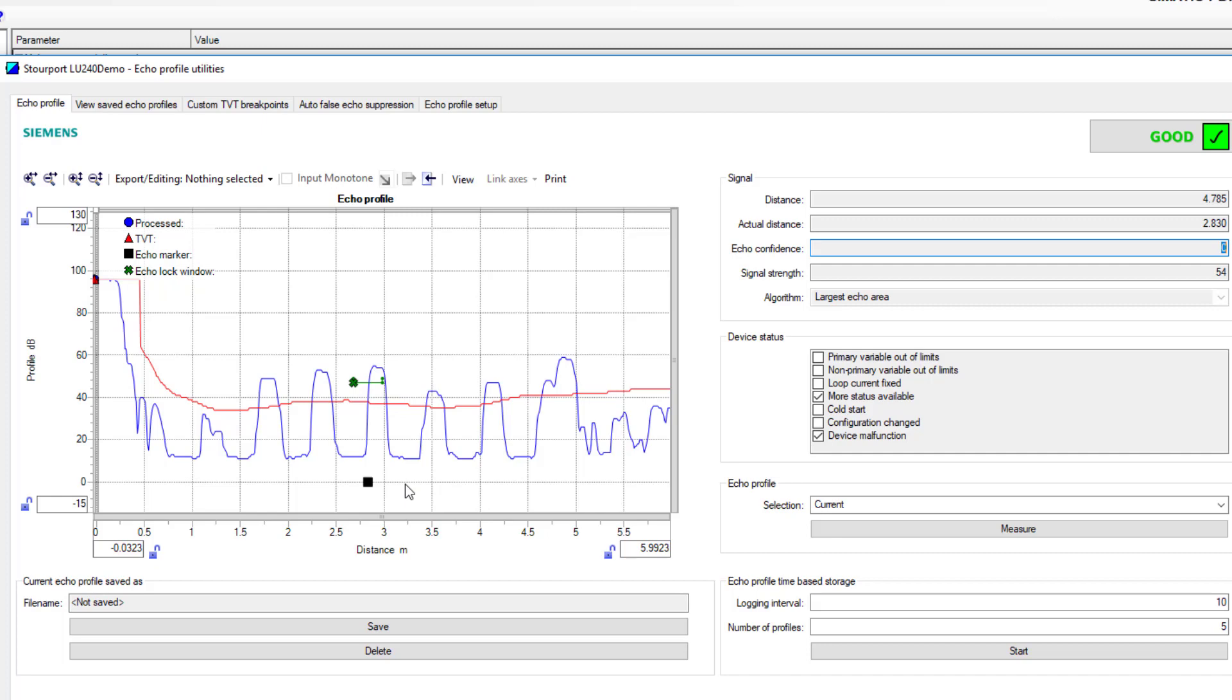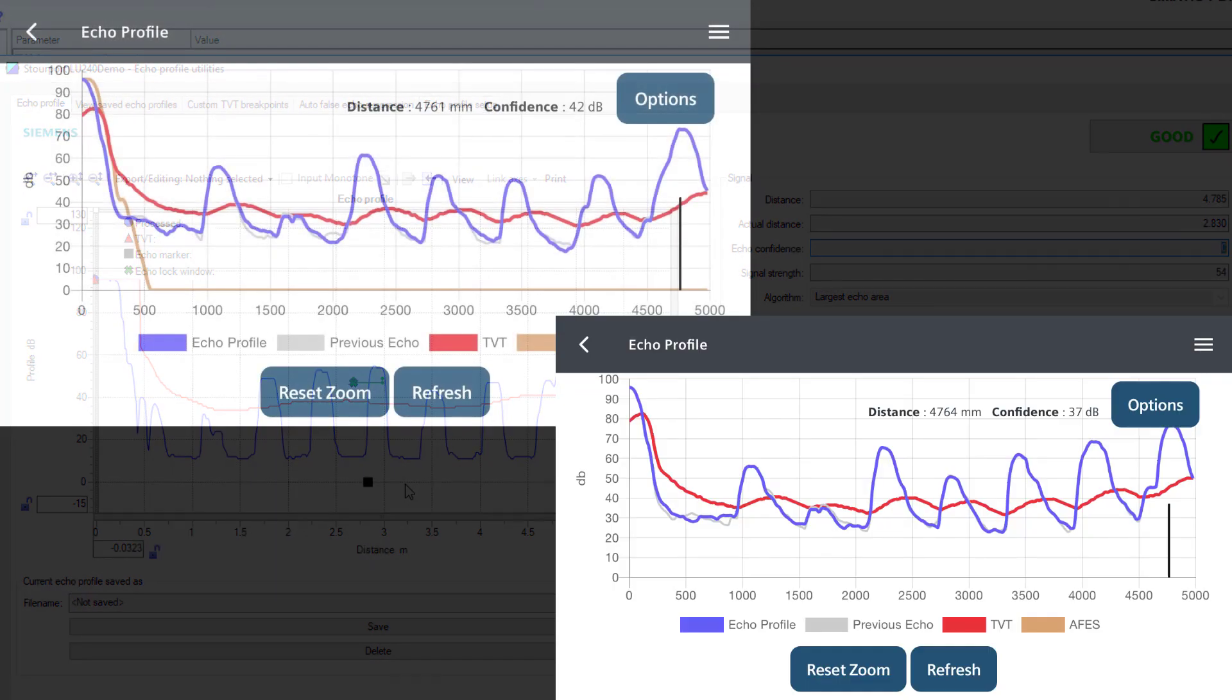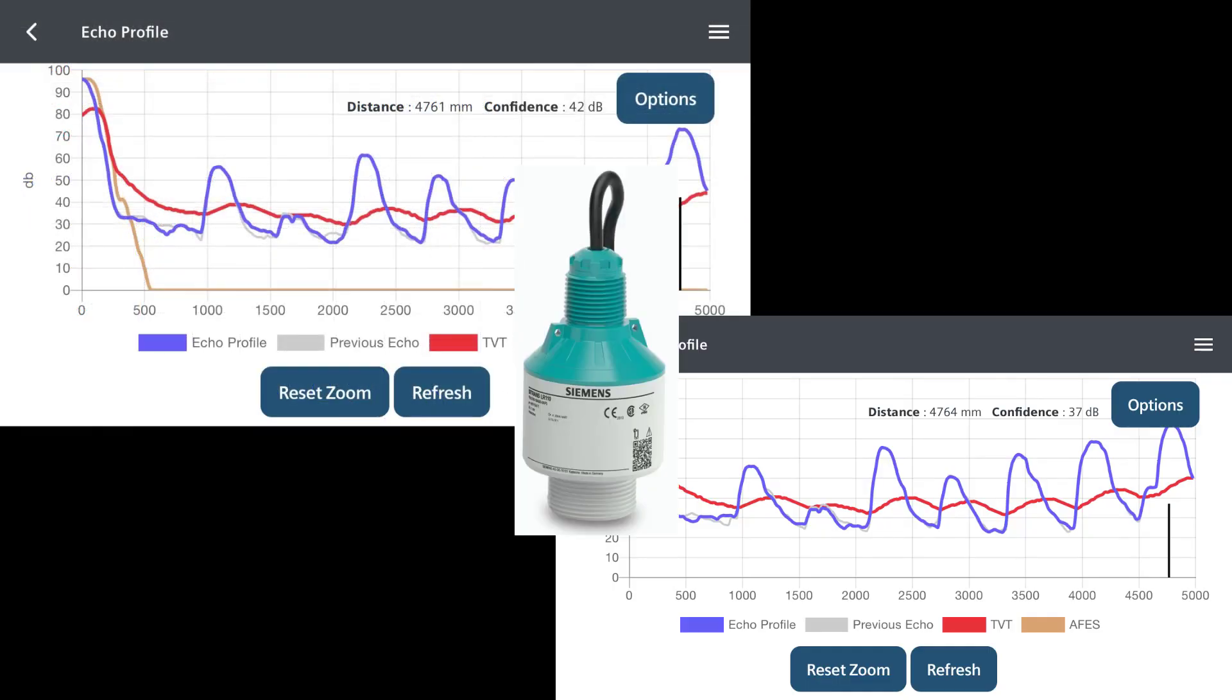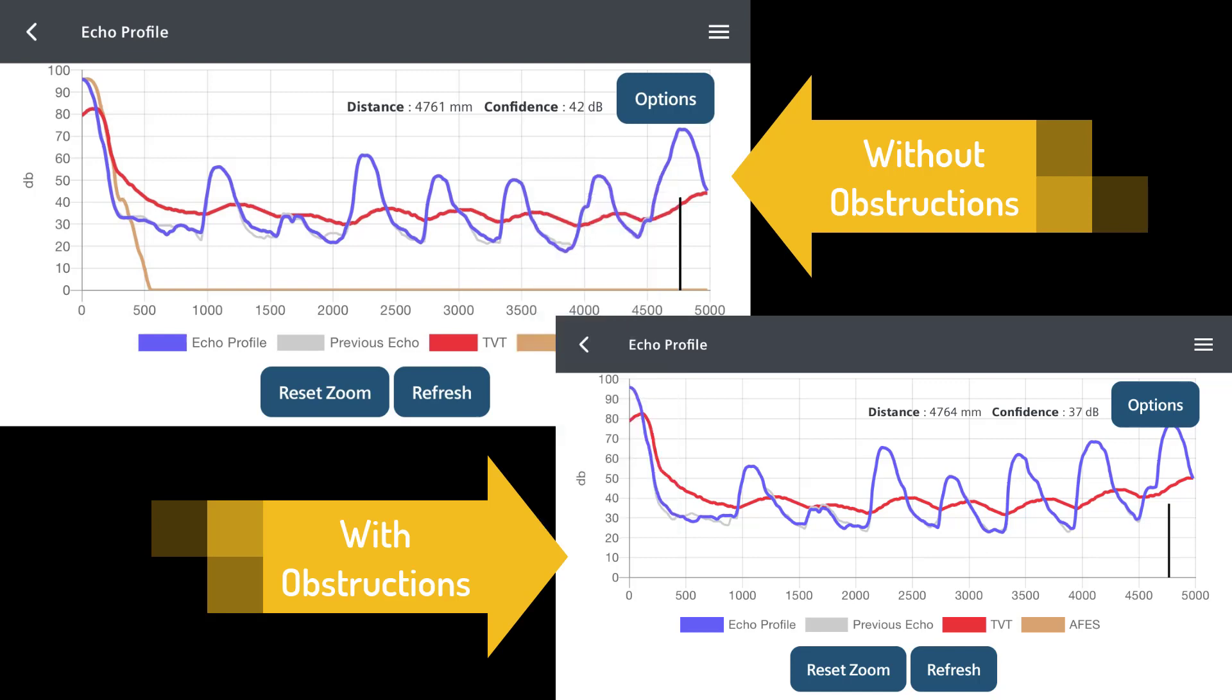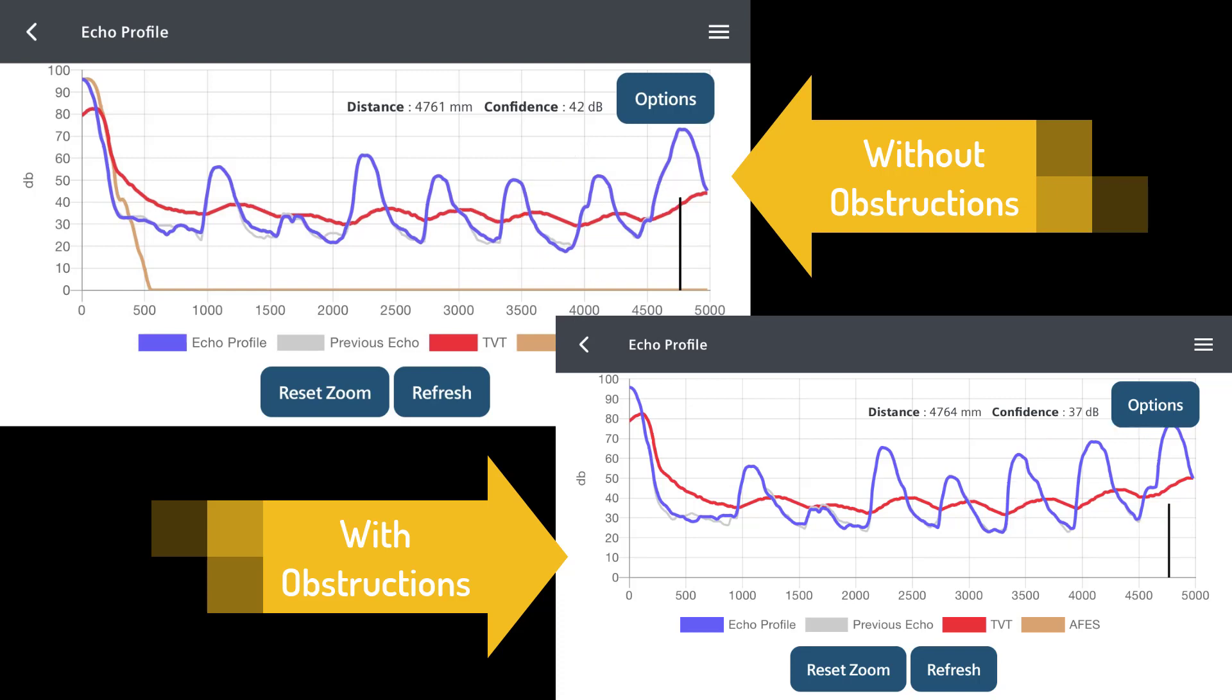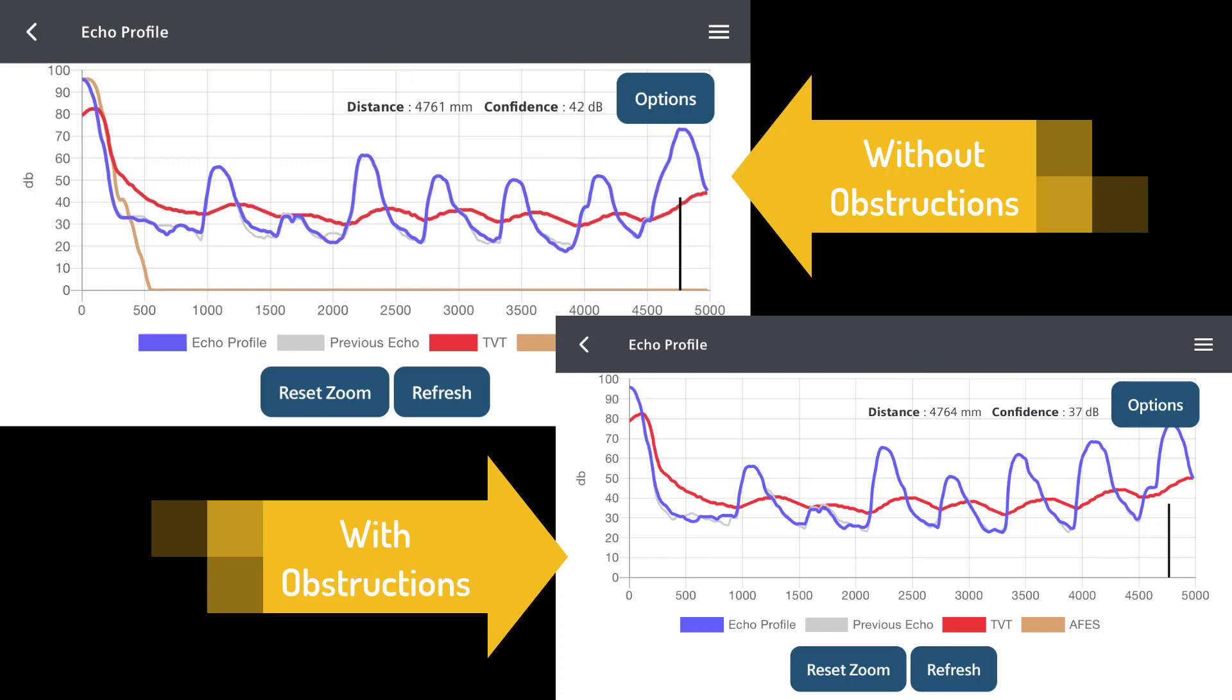Now we'll have a look at the radar, the SITRANS LR110. This device is performing extremely well with all these obstacles. In fact there's only one of the obstacles potentially that's creating a larger echo and that's the aluminum steps. You can see a slight attenuation in the confidence and a slight movement in the actual distance value, but considering what's been put in front of it, a three or four millimeter movement is absolutely fantastic. This little radar is looking very, very good.